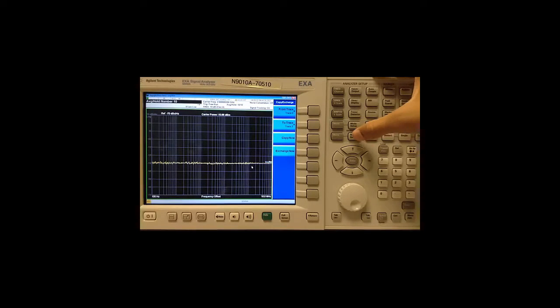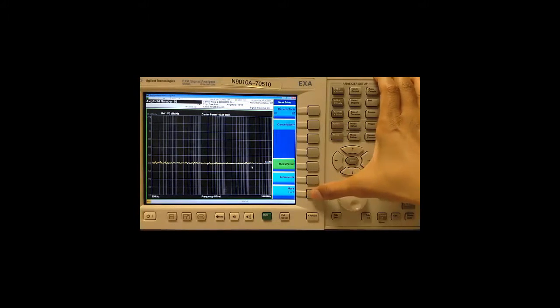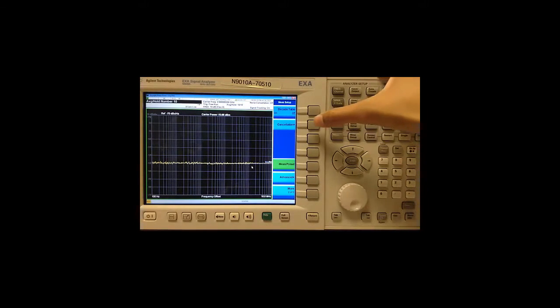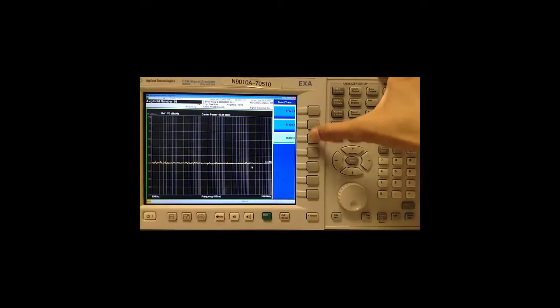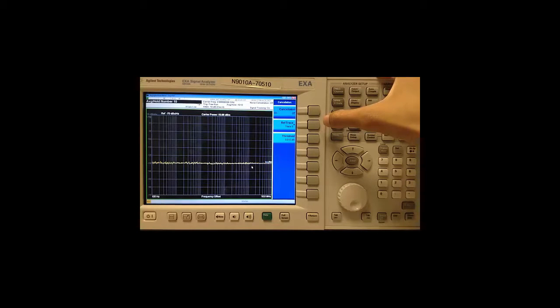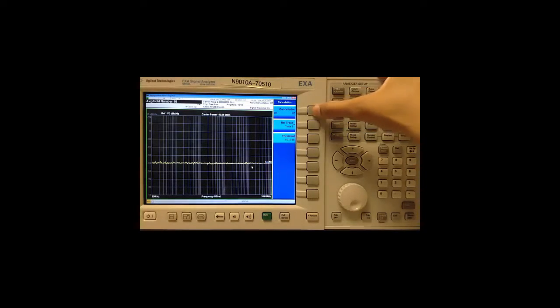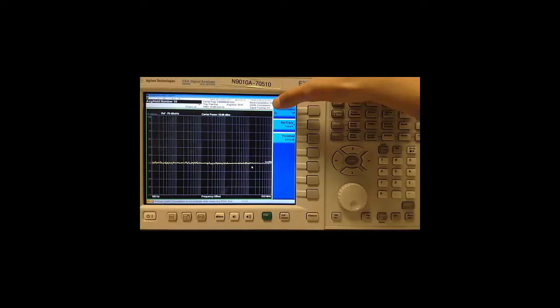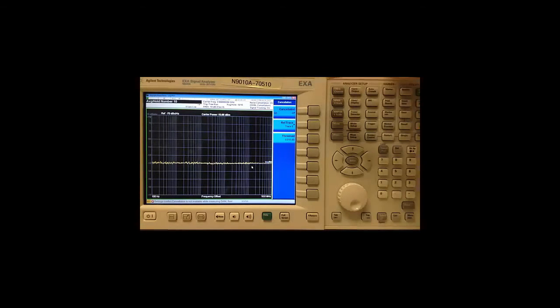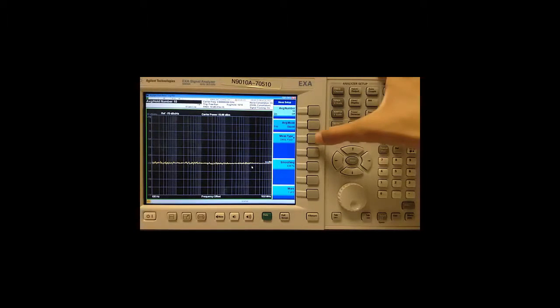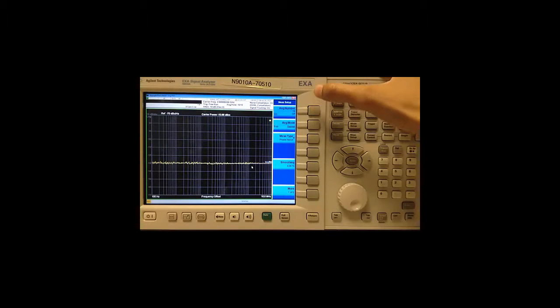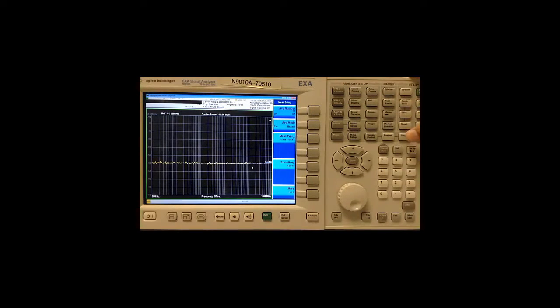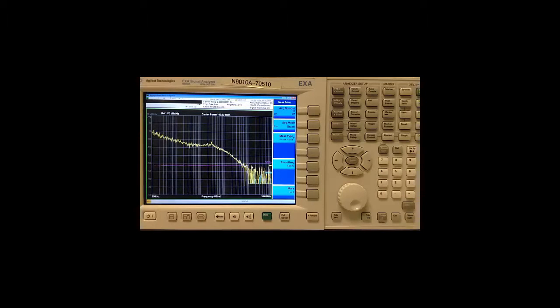Next we go to measure setup, more, cancellation. Make sure our reference trace is trace 3 which contains a copy of our smooth trace measured from the noise floor. Turn cancellation on and you can see it update here. Go to measure setup, change back to phase noise and then push restart to make a fresh measurement. And that's how you do cancellation.